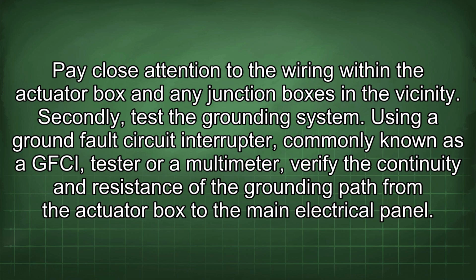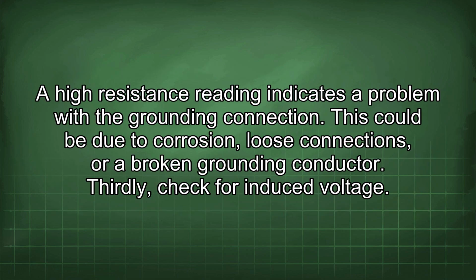Secondly, test the grounding system. Using a ground fault circuit interrupter, commonly known as a GFCI tester, or a multimeter, verify the continuity and resistance of the grounding path from the actuator box to the main electrical panel. A high resistance reading indicates a problem with the grounding connection. This could be due to corrosion, loose connections, or a broken grounding conductor.